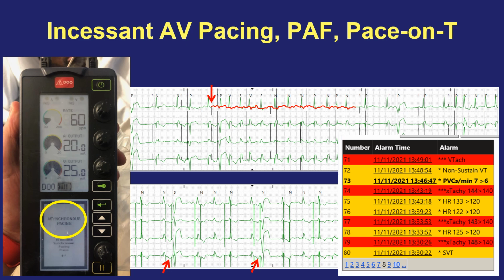And you can see, first of all, asynchronous pacing is occurring, and that's shown here at the bottom window of the bedside temporary pacemaker. But in addition, when the emergency button was hit, that's this, DOO, this emergency button, not only does it make the device pace in a DOO asynchronous mode, but it cranked up the outputs to max. This is a bad combination because it isn't simply that the pacing spike was occurring in a vulnerable period in the atrium or a vulnerable period in the ventricle, but if you crank up that output, you're more likely to cause atrial fibrillation or polymorphic ventricular arrhythmias when you're pacing on a T wave.